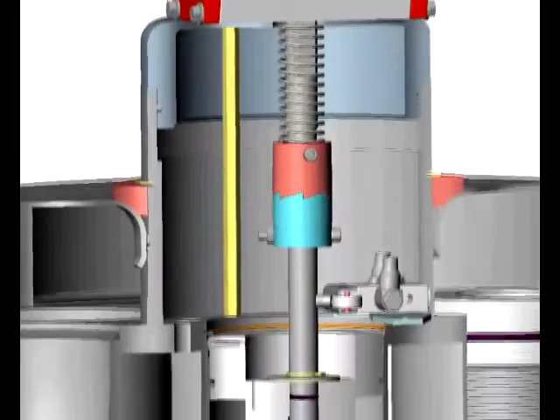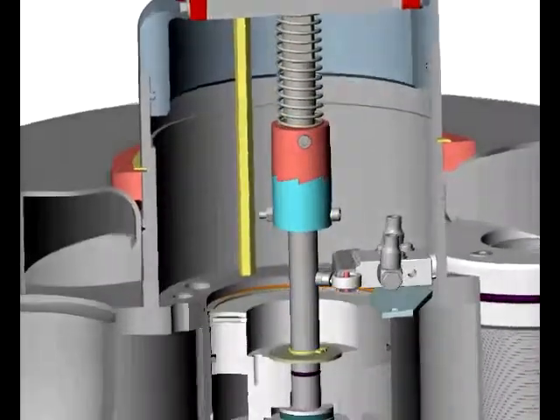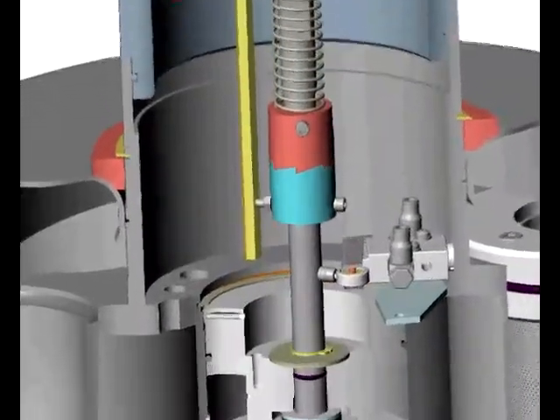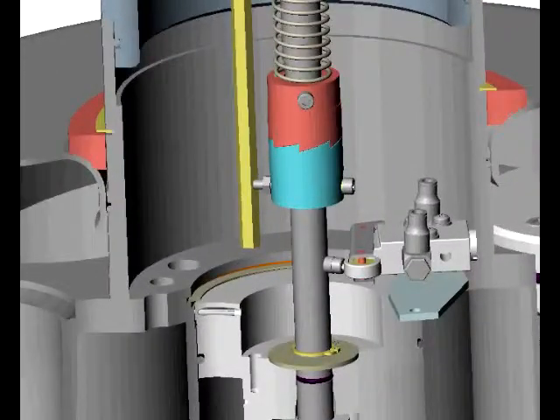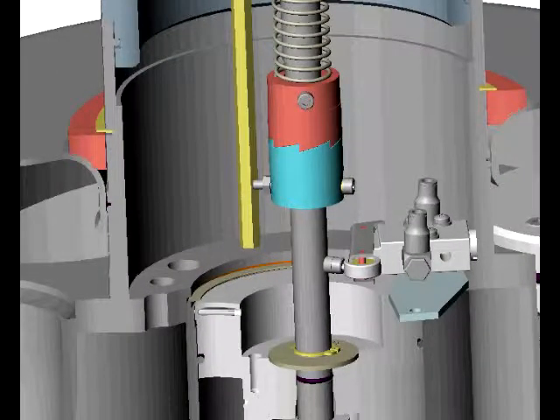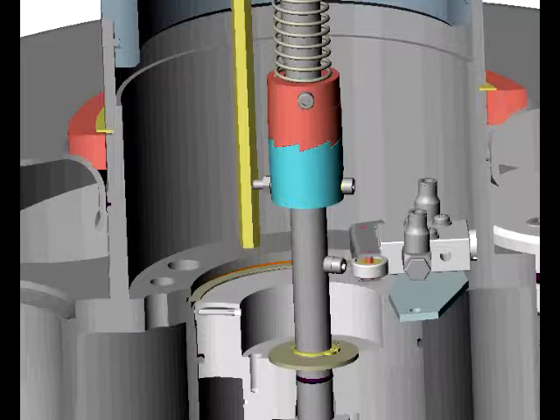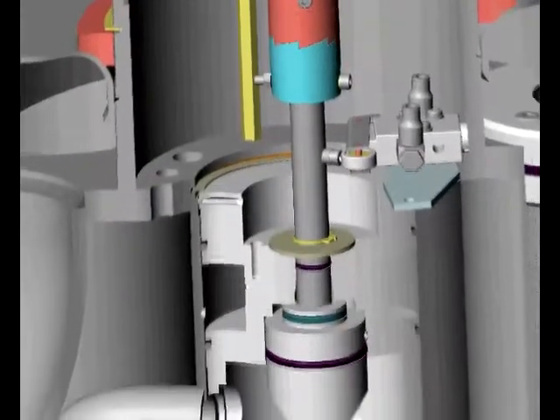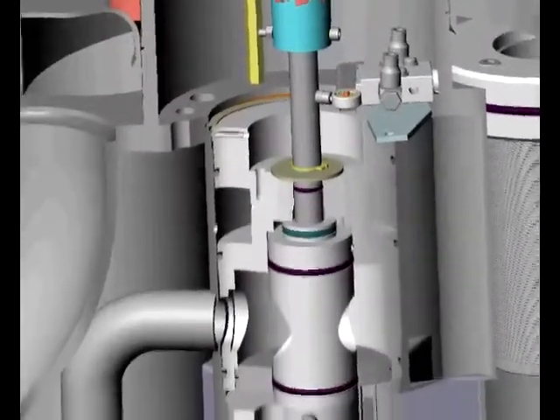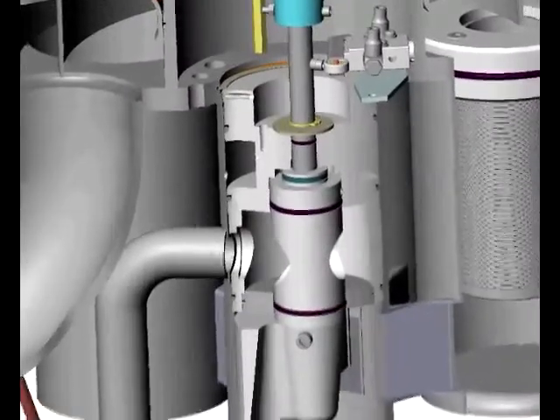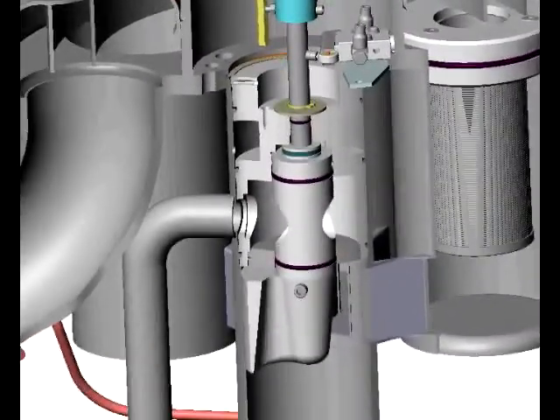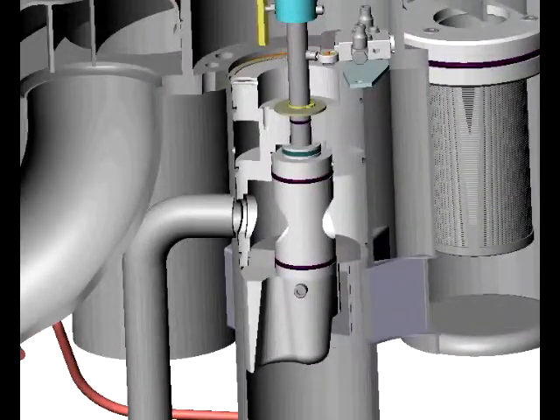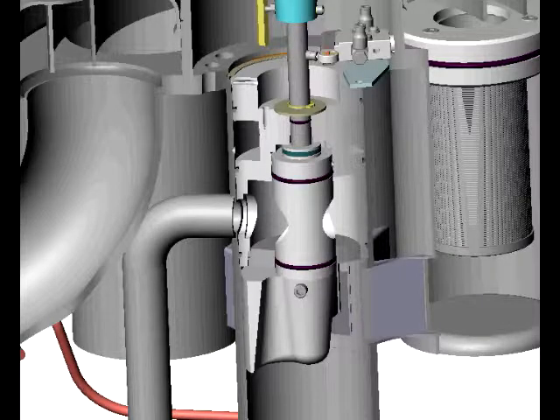The lower drive shaft has a protruding screw which in the position shown depresses the roller arm of the home position roller valve. The function of this roller valve is to tell the control system that the filter's home position has been found. The lower drive shaft passes through the body of the indexing valve and is connected to the shoe in the inlet tube of the filter. We have returned the shoe to its home position where it is not obscuring any of the rectangular inlet galleries to the six filter pods.